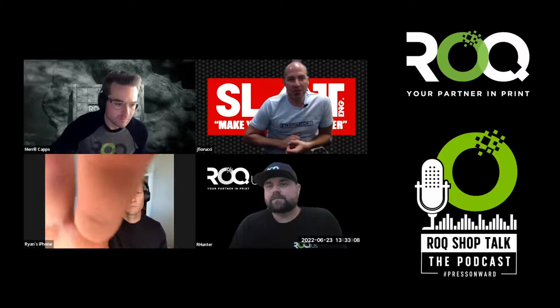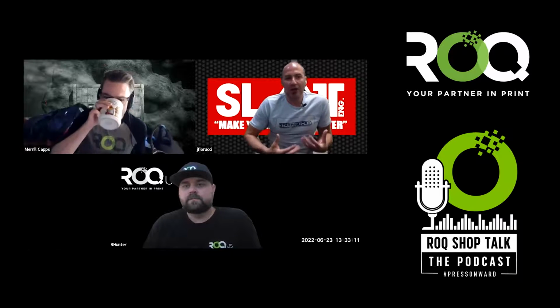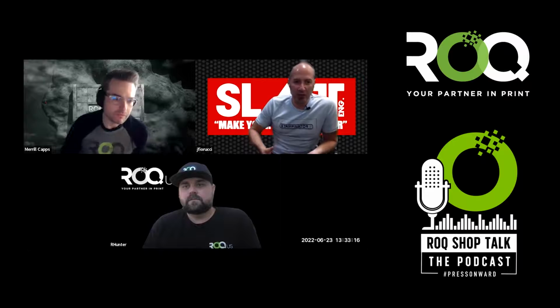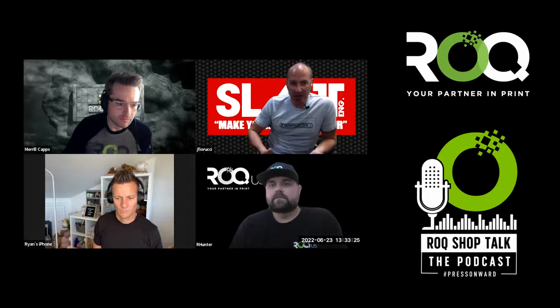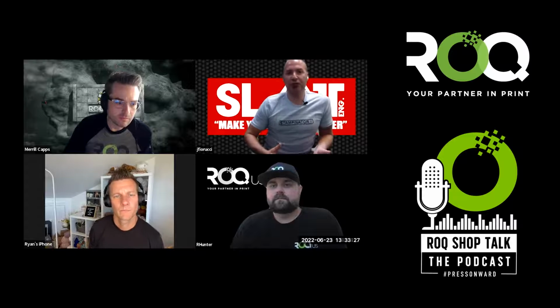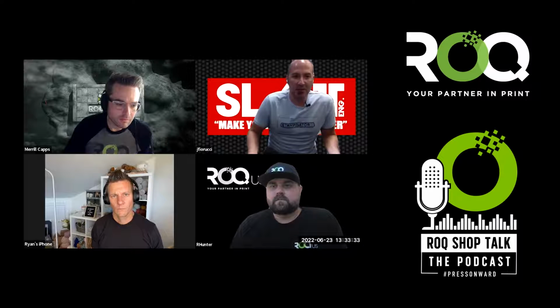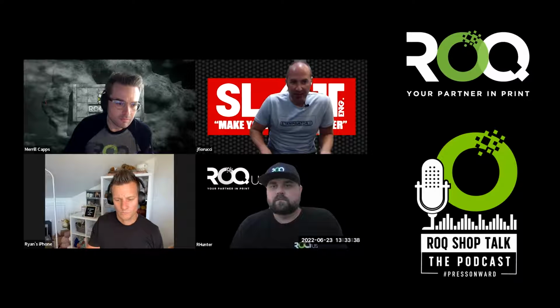Yeah. So some of the things that you need to think about in your shop: first of all, the Stampinator is a single phase unit. So it's 220, 240. It's 3,500 watts. It draws 17 amps. So you need a 30 amp breaker. Your plug adapter needs to be a 30 amp. You can plug it into any type of press that is a 3-phase. You just end up dropping one of the legs in the 3-phase. You cut that back or have your electrician do that. And you can run as long as you're getting 125 out of each leg or 115 out of each leg to get your 220.